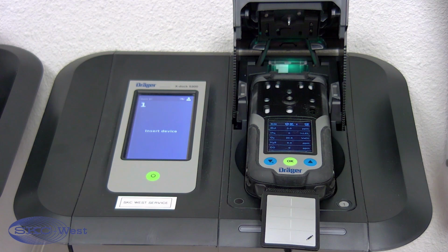When the X-Dock is first set up, all of the gases and demand flow regulators should be configured so that the calibration and bump test sequence should go flawlessly. It is very important to get the gases on the correct ports if you have multiple gases. Please give our office a call should you have any questions or need assistance. To begin a bump test or calibration, be sure to remove the pump test adapter before sliding the instrument into the correct bay. Close the lid and the X-Dock does the rest.